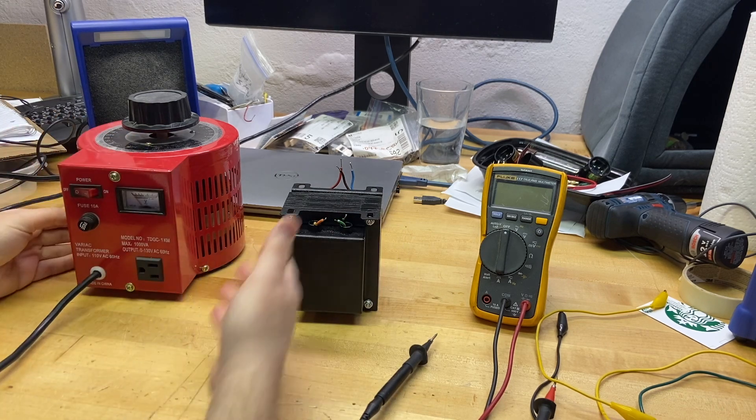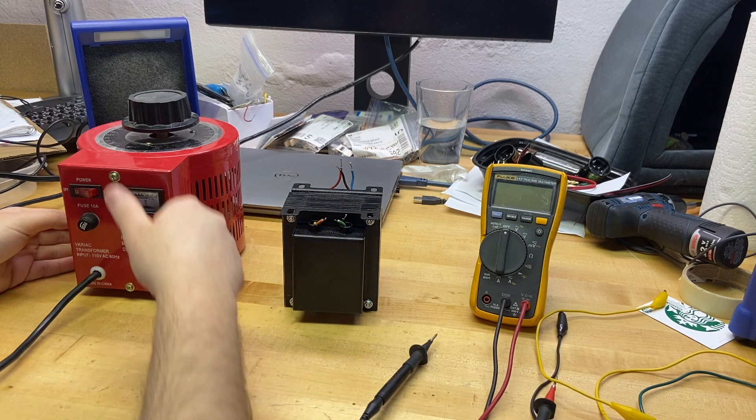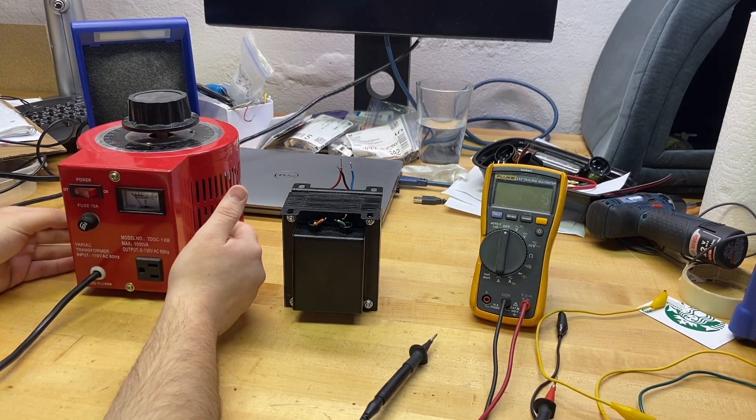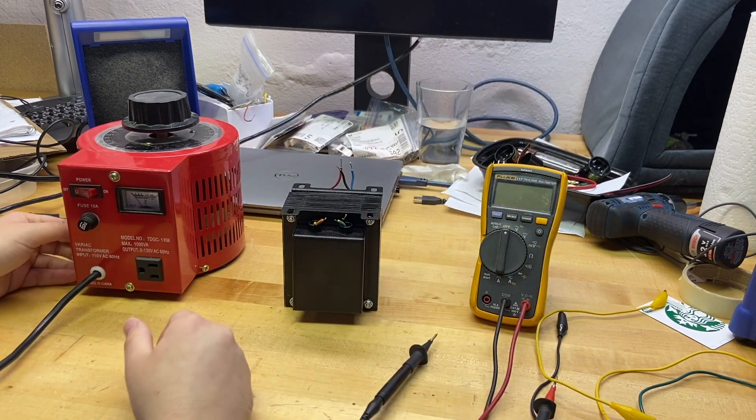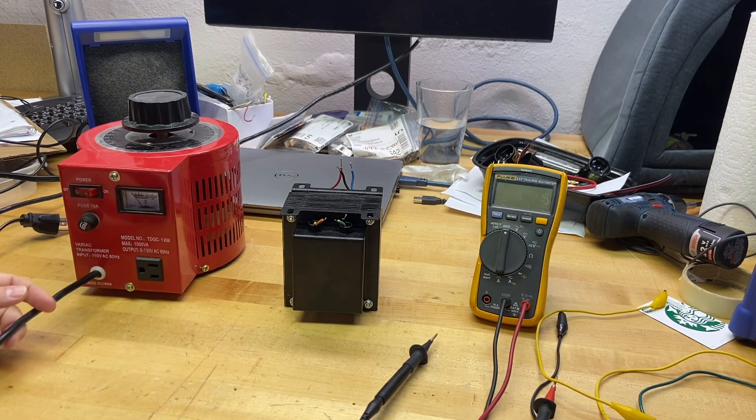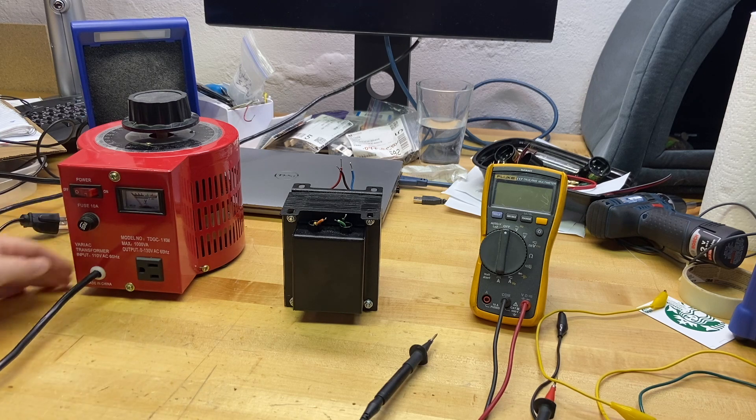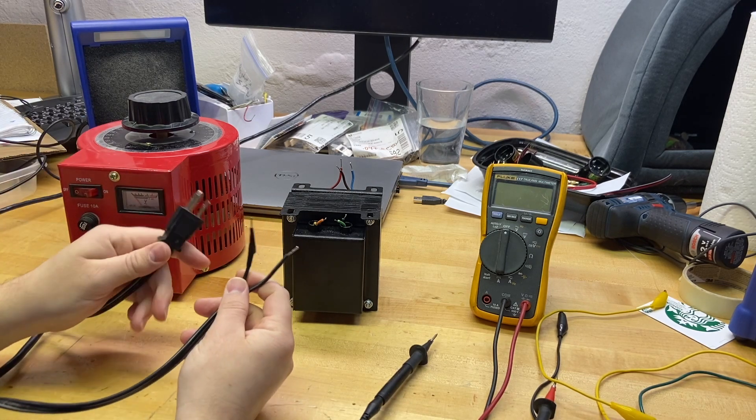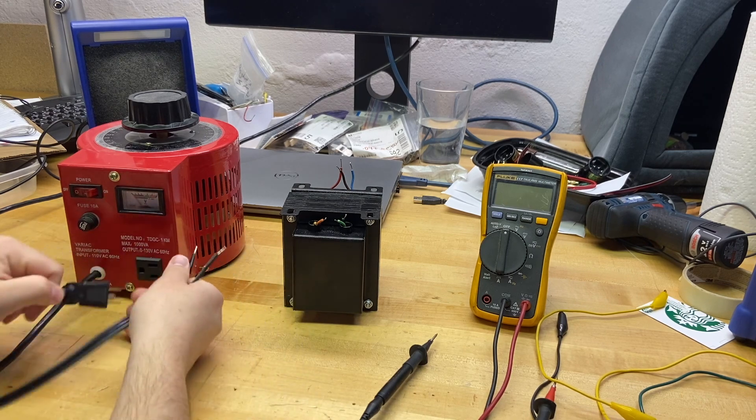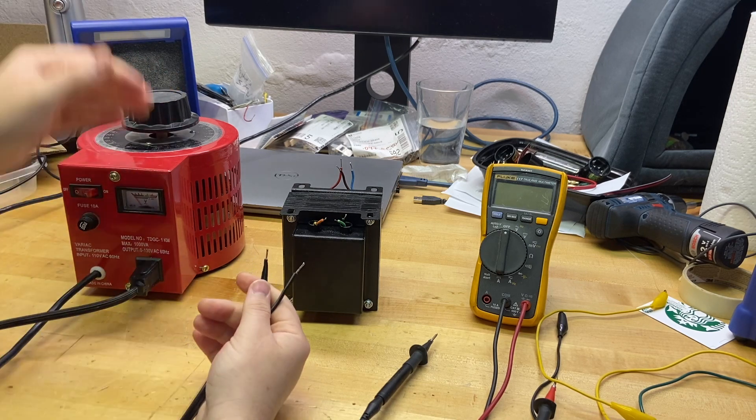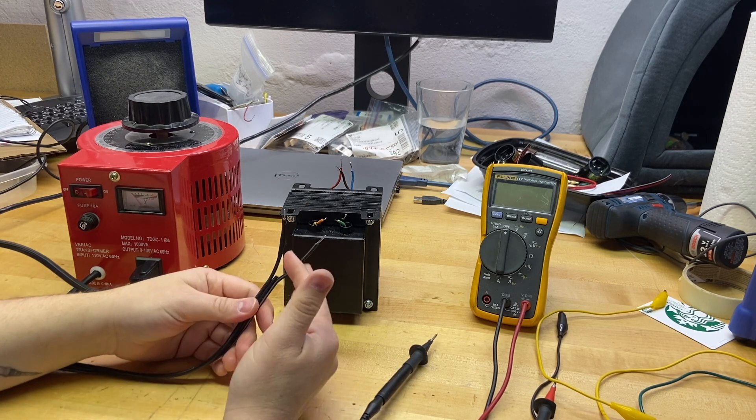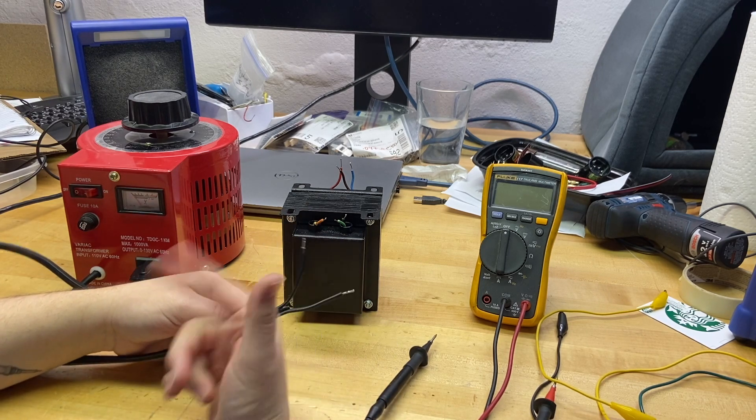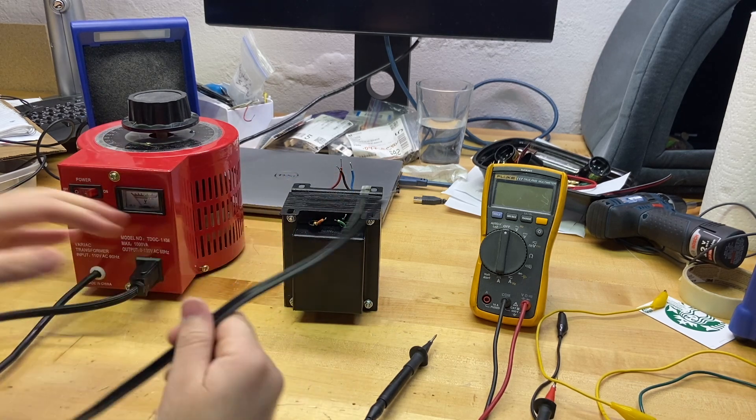So in order to do that test, I've got to have the unit under test, a variac that we can put the correct voltage out that we want, and then our handy voltmeter. I've got the variac off, very important to start with it off. I've got it plugged into just a power strip on my bench. I made a nice sort of janky little power cable that we're going to use for this test. This is our output on our variac. This is our neutral and this is our line, and then the ground wire was here, and I snipped it because we don't need it.